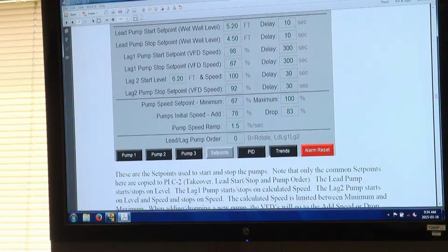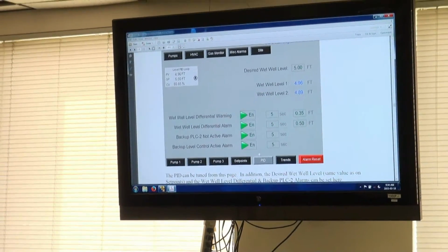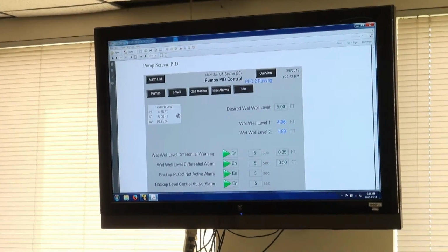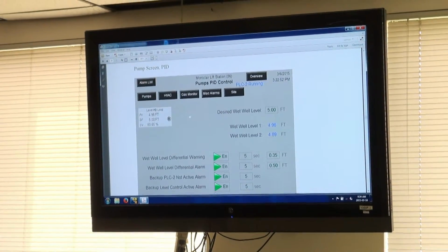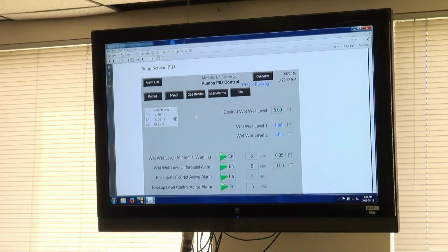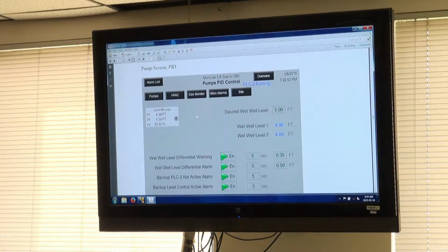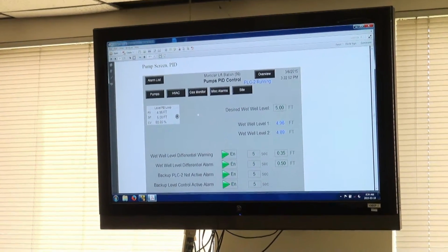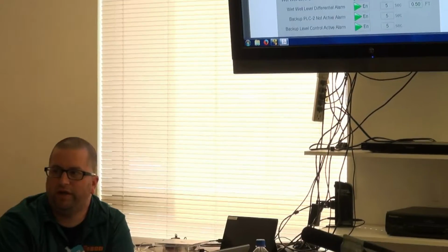Any questions on the controls for PLC 1? Your PID page, this is where we would set up our PID. Currently we don't have a manual PID, so that situation that happened at Philadelphia won't happen here. I'm going to talk with Mike. We may add that manual PID, and that would basically force the PID to stop calculating. Sometimes you guys, Mike explained it, you want to run the pumps and continue to run them down. What you can do is put the pumps in manual and adjust the manual speed, and that'll prevent that.